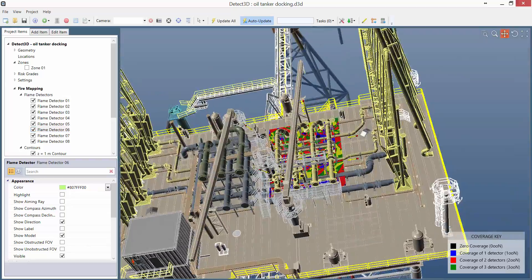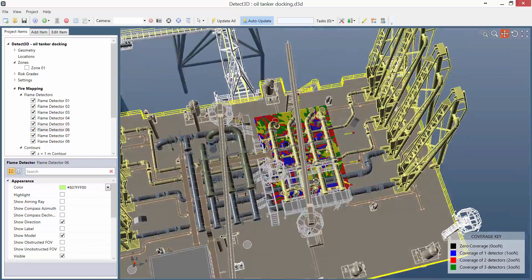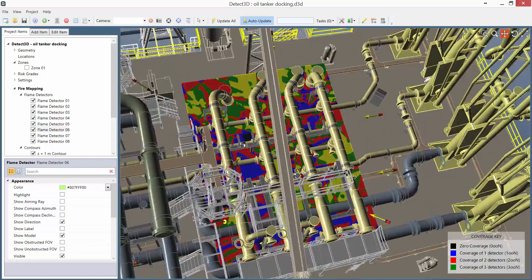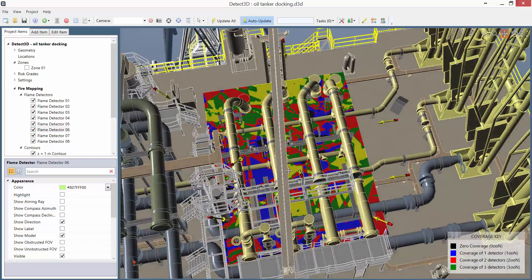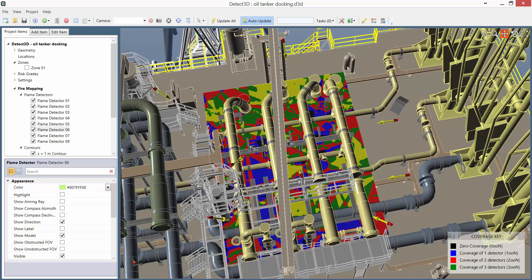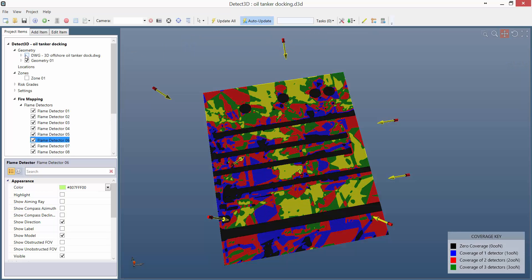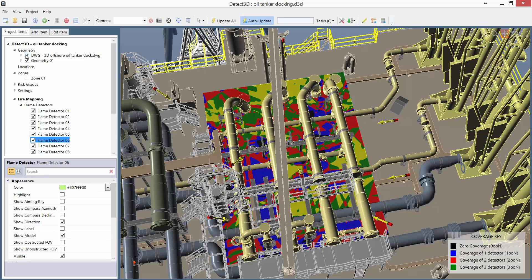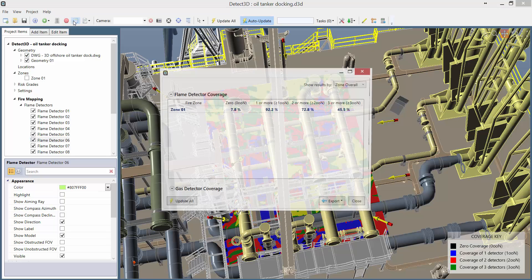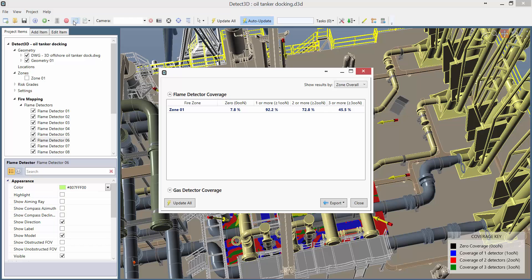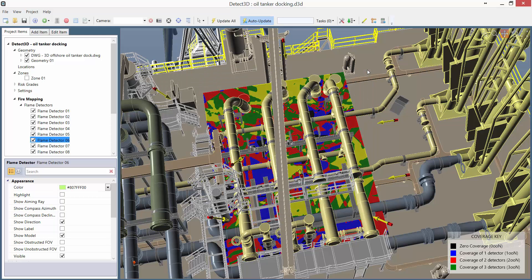I have one here at 1m above the zone level. The red, green and yellow areas show that I've got pretty good coverage. If I just switch the geometry off we can see that more clearly. Looking at the coverage statistics, we've got 92% covered by one or more and 72% covered by two or more detectors.